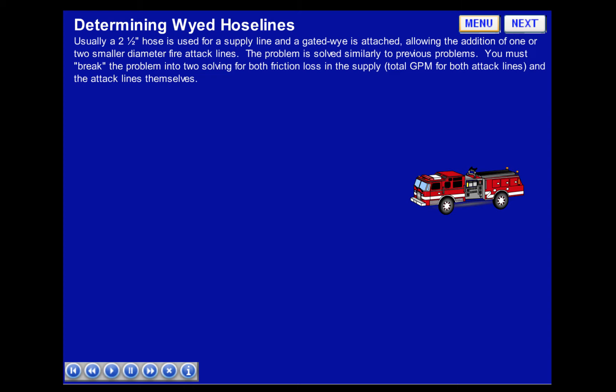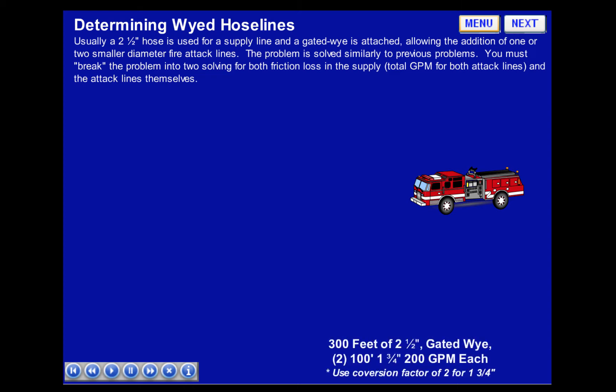The problem is solved similarly to previous problems. You must break the problem into two parts, solving for both friction loss in the supply total GPM for both attack lines, and the attack lines themselves. In this scenario, the firefighters are ordered to pull 300 feet of 2.5-inch hose, attaching a gated wye and flowing two 100-foot, 1¾-inch hose lines, each flowing 200 GPM.